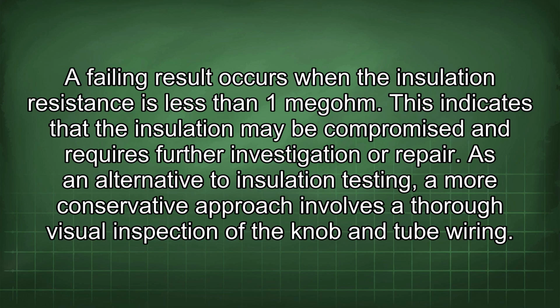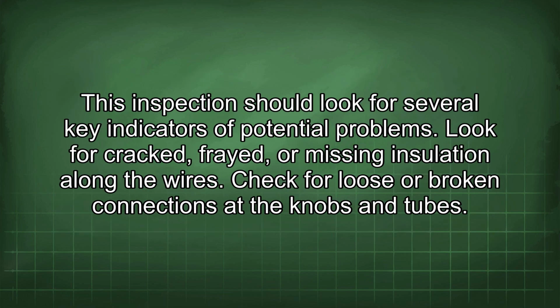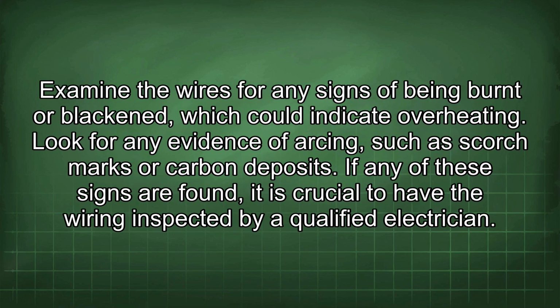As an alternative to insulation testing, a more conservative approach involves a thorough visual inspection of the knob and tube wiring. This inspection should look for several key indicators of potential problems. Look for cracked, frayed, or missing insulation along the wires. Check for loose or broken connections at the knobs and tubes. Examine the wires for any signs of being burnt or blackened, which could indicate overheating. Look for any evidence of arcing, such as scorch marks or carbon deposits.